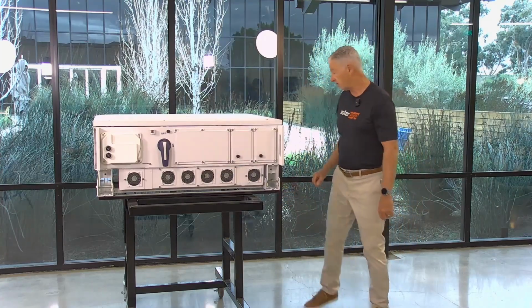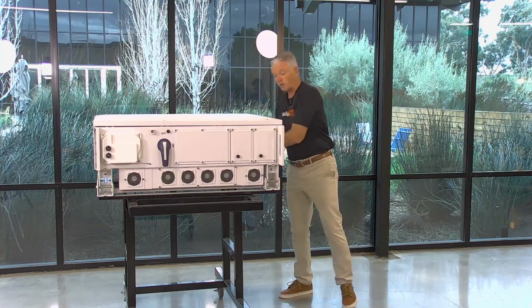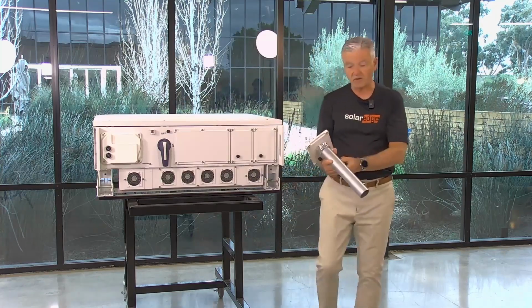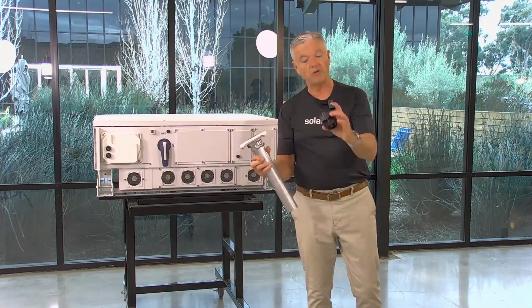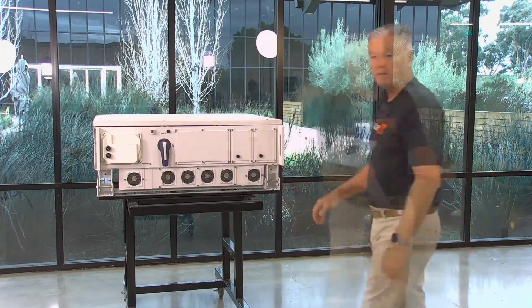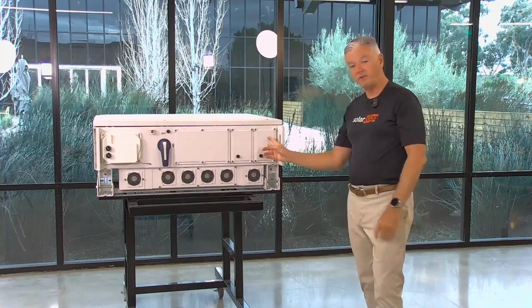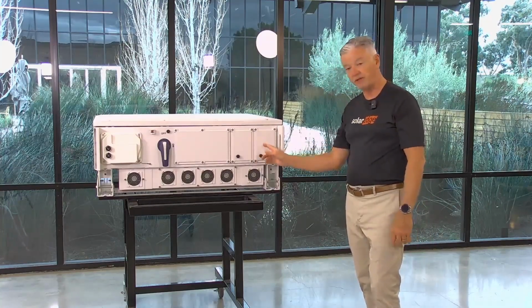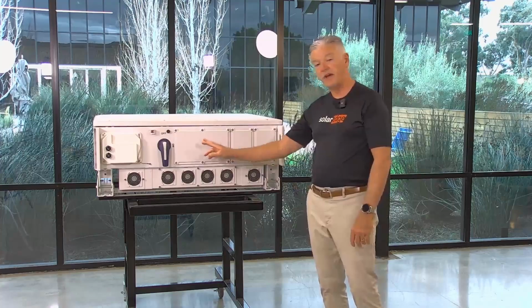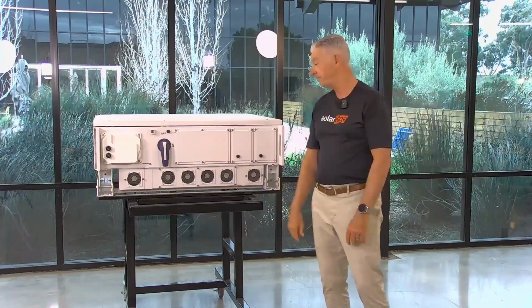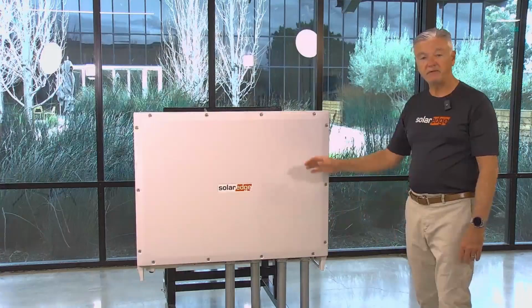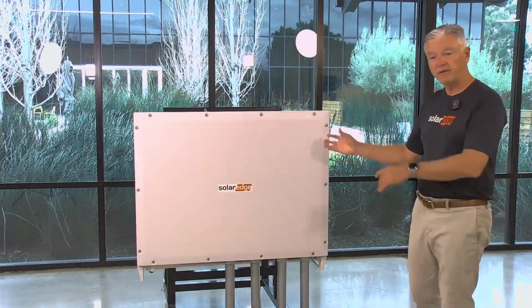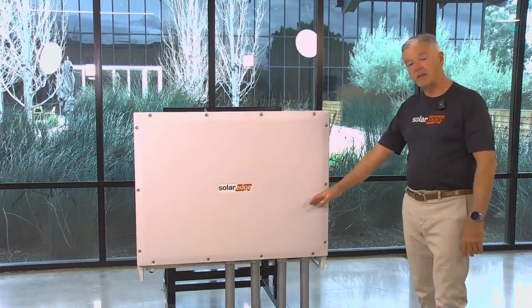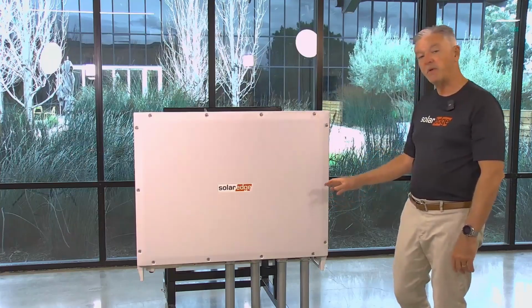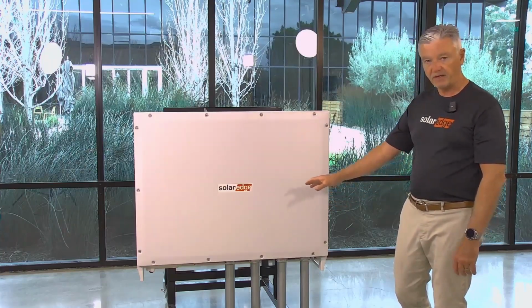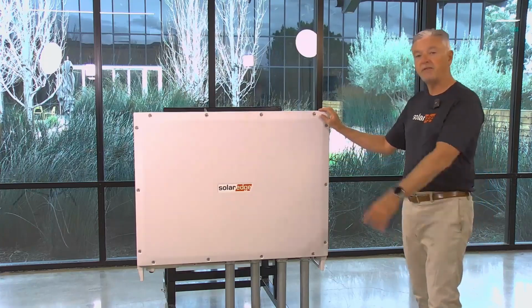Entry into the inverter enclosure can be done with conduit or with cable glands. This is what it looks like with conduit, and you can also use something like this, a cable gland. The AC conduit size is up to 2.5 inches on both of these conduit plates, and for the DC side, up to 2 3-inch conduits. Now that we've seen what the bottom of the inverter looks like, we've flipped it back up, and for our example, we've installed 2-inch conduit on both the AC side and the DC side. Now let's take the cover off and have a look inside.